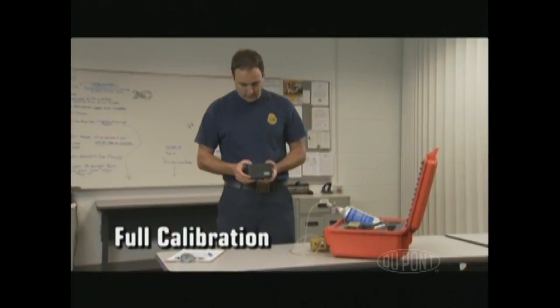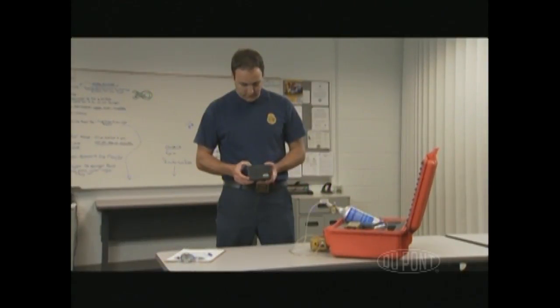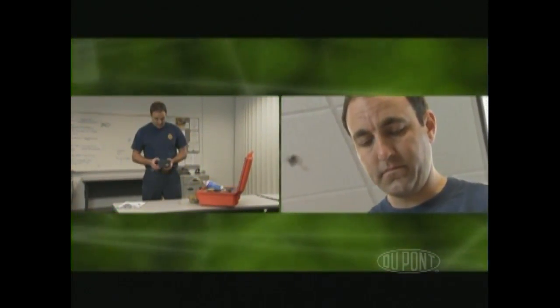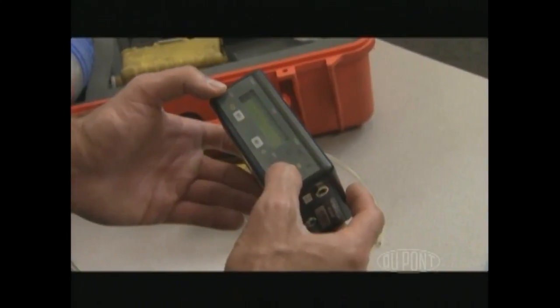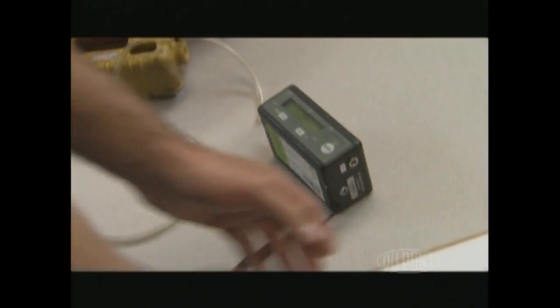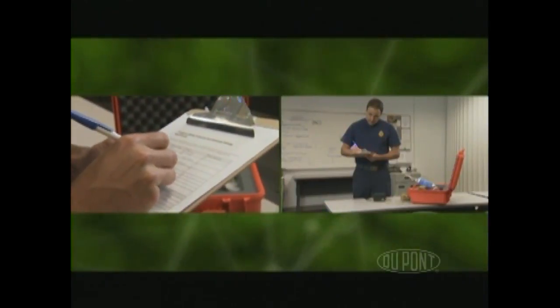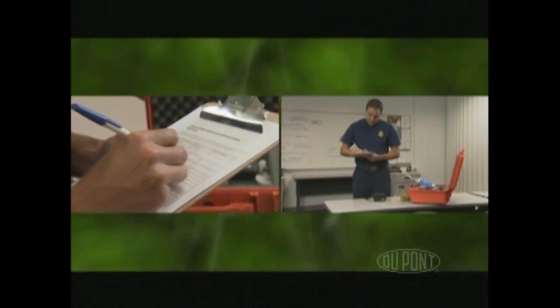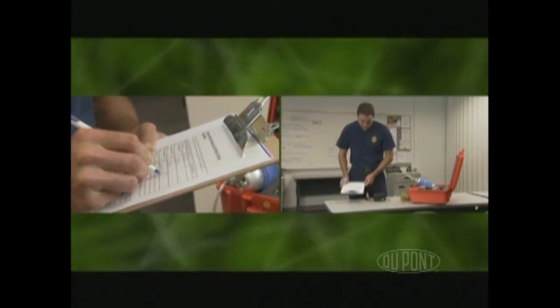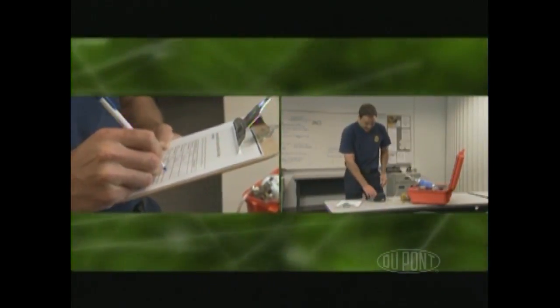Full calibration involves adjusting the instrument's reading to coincide with a certified concentration of test gas. Any adjustments should be made by a qualified professional and follow the manufacturer's recommended calibration frequency and procedure. Keep an updated record of each instrument's calibration to meet safety standard requirements, as the best way for an employer to verify calibration is through documentation.